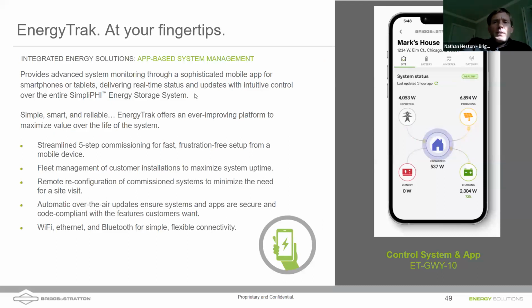Again, EnergyTrak makes a big difference. It's our monitoring platform. It allows us to see where the power is going, and it offers very fast commissioning. I can commission our inverter systems after they're set up in less than 10 minutes. It also allows fleet management, which means that you can see all of the inverters and the ESS systems that you've installed, and it allows remote configuration of commissioned systems so that you can make changes from a distance.